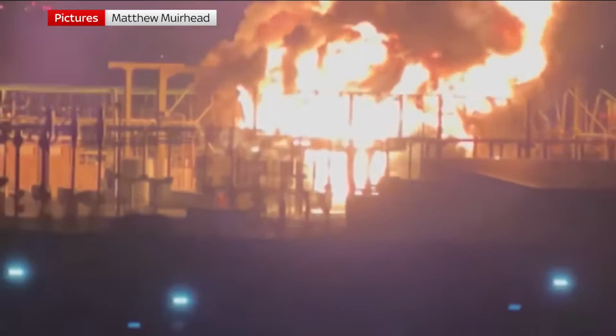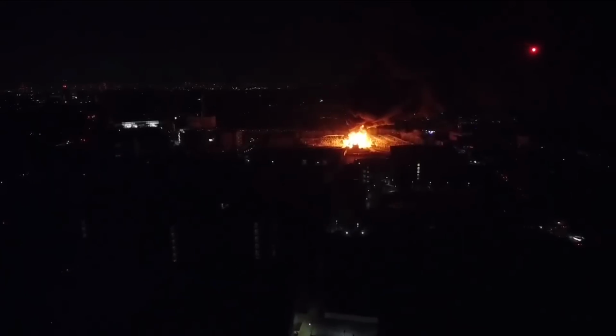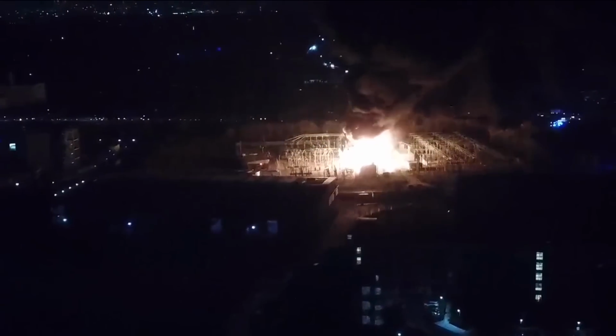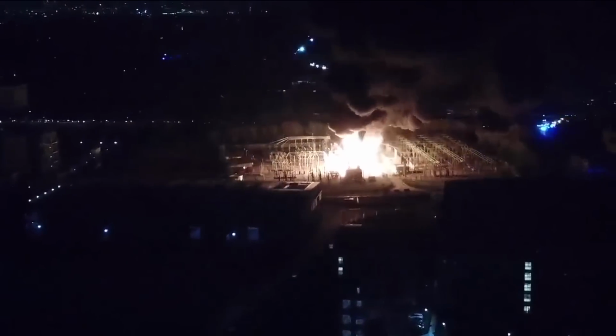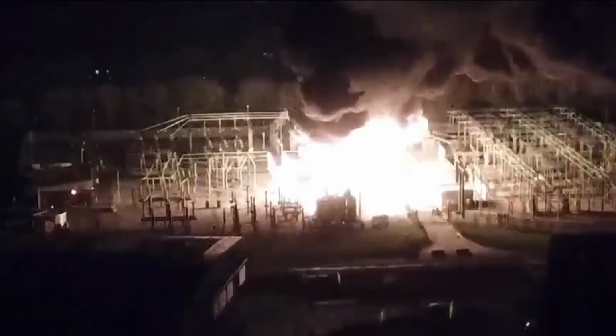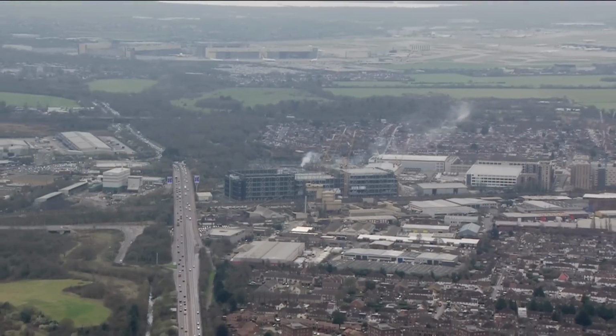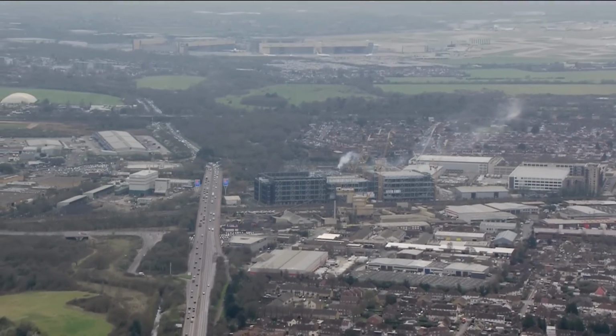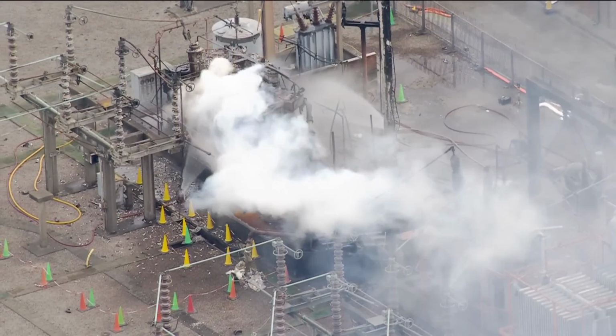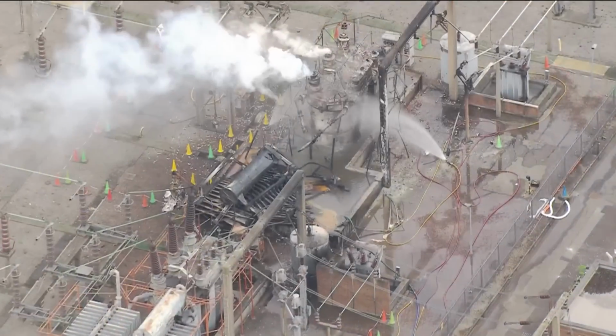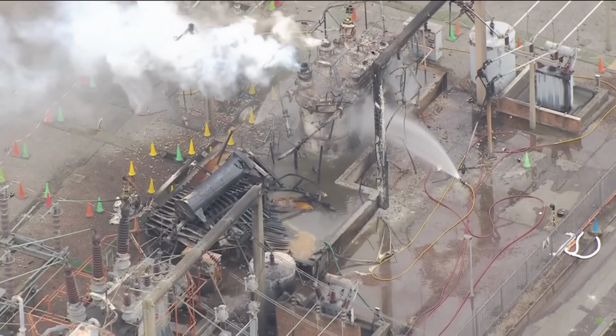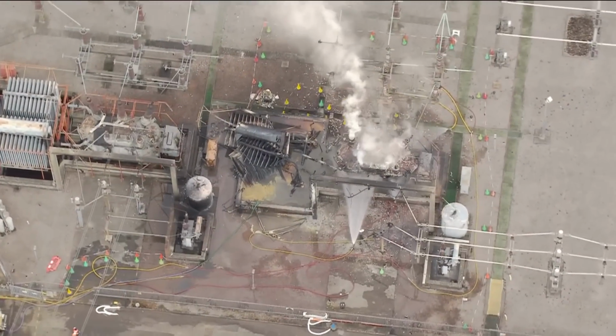The fire that cut the power, that shut down Heathrow, that affected 1,300 flights carrying nearly 300,000 passengers around the world, was entirely preventable. The report into the outage at National Grid's North Hyde substation found that moisture build-up which led to a catastrophic transformer failure was picked up 7 years previously and not acted on.